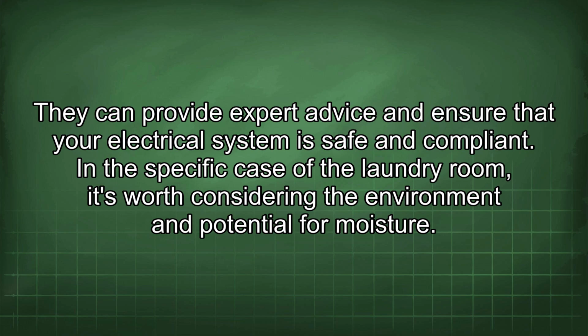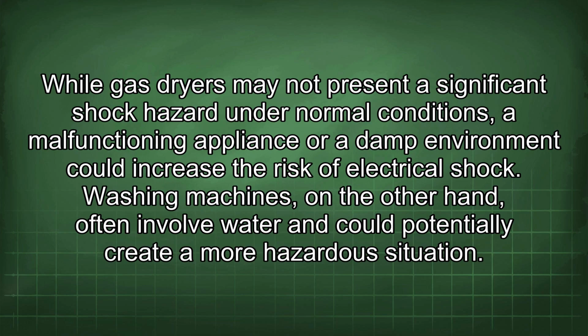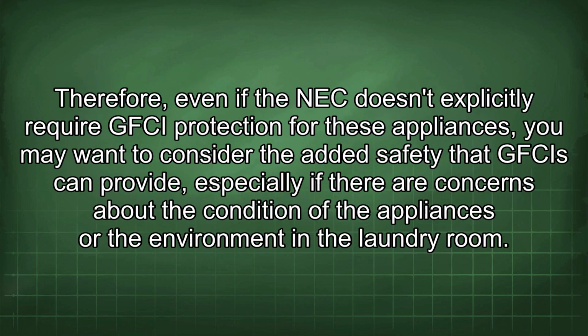In the specific case of the laundry room, it's worth considering the environment and potential for moisture. While gas dryers may not present a significant shock hazard under normal conditions, a malfunctioning appliance or a damp environment could increase the risk of electrical shock. Washing machines, on the other hand, often involve water and could potentially create a more hazardous situation. Therefore, even if the NEC doesn't explicitly require GFCI protection for these appliances, you may want to consider the added safety that GFCIs can provide, especially if there are concerns about the condition of the appliances or the environment in the laundry room.